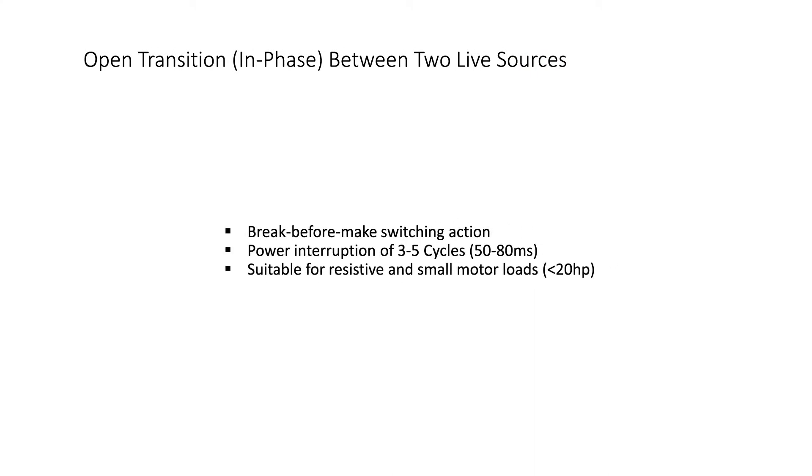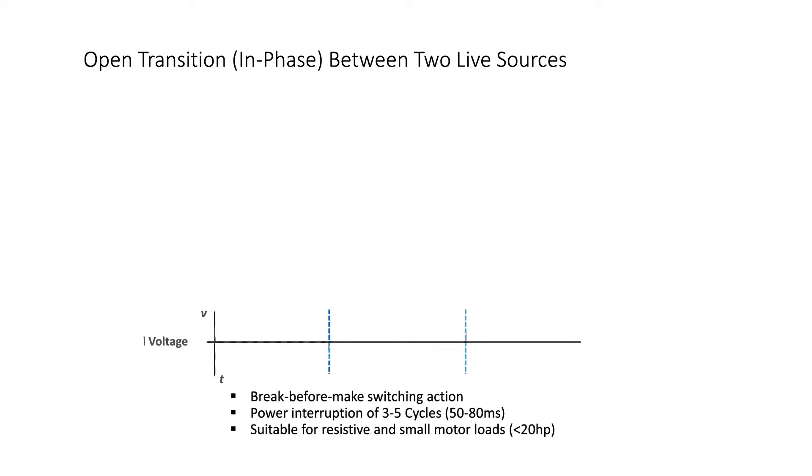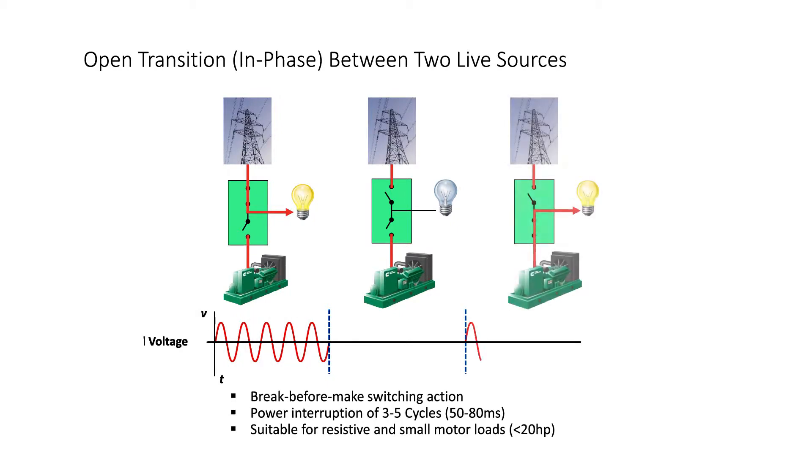In a simple open transition operation between two live sources, the connected loads experience power interruption for 50 to 80 milliseconds. This transition type is suitable for resistive and small motor loads less than 20 horsepower.